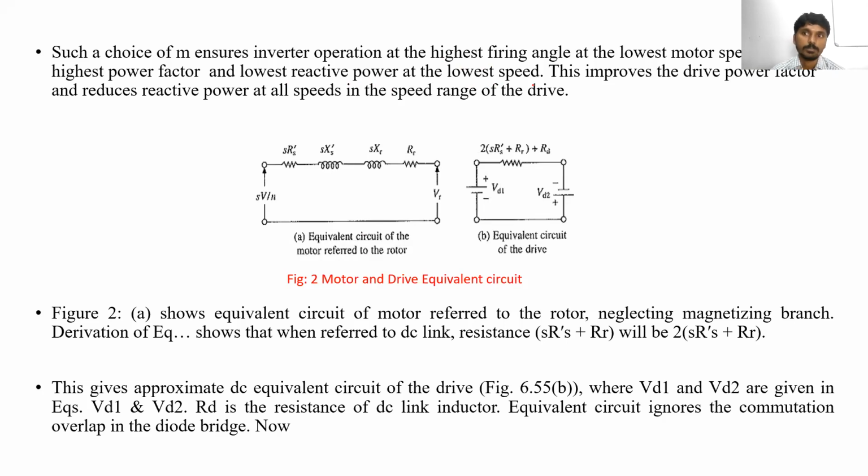This improves the power factor and reduces the reactive power at all speeds in the speed range of the drive. So by decreasing the reactive power and increasing the power factor, the total efficiency of the drive system can be increased. Clear?